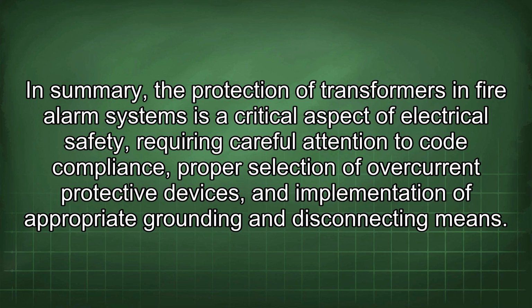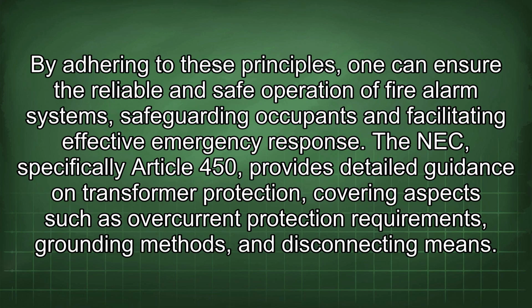In summary, the protection of transformers in fire alarm systems is a critical aspect of electrical safety, requiring careful attention to code compliance, proper selection of overcurrent protective devices, and implementation of appropriate grounding and disconnecting means. By adhering to these principles, one can ensure the reliable and safe operation of fire alarm systems, safeguarding occupants and facilitating effective emergency response. The NEC, specifically Article 450, provides detailed guidance on transformer protection, covering aspects such as overcurrent protection requirements, grounding methods, and disconnecting means.